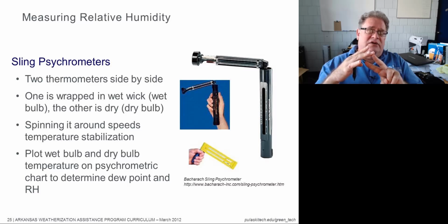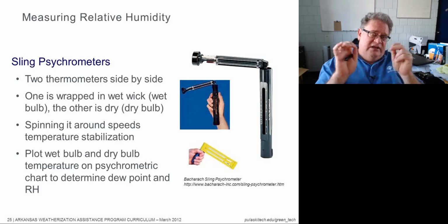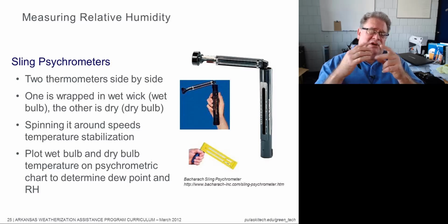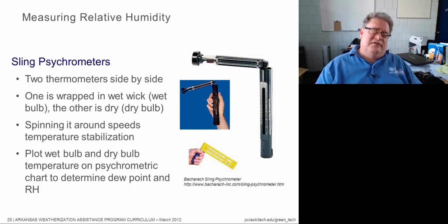The other thermometer can only go as low as air temperature, so it will stop at air temperature. This other one will stop when we can't put enough energy into it to keep evaporating water off of that wick. The difference between those two, you then look on the outside of this thing and read the scale on it, and it says this is the wet bulb temperature and this is the dry bulb temperature. Once your temperature is stabilized and you've read it, you plot that out and it will tell you you're about 78% or 68% relative humidity. Sometimes you have to plot it out on a chart to determine it. There are electronic versions of this that are a lot easier. You just read a number off of it.